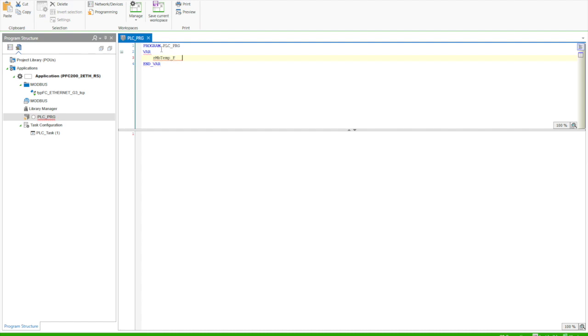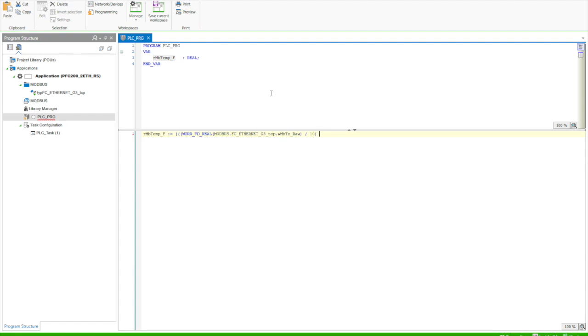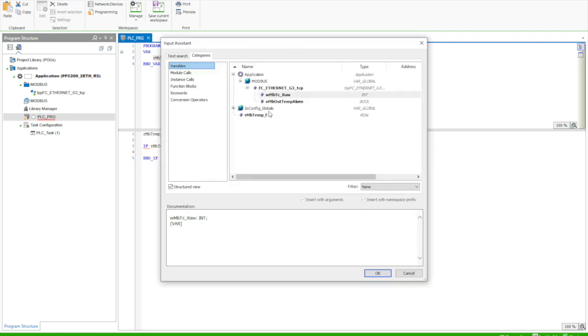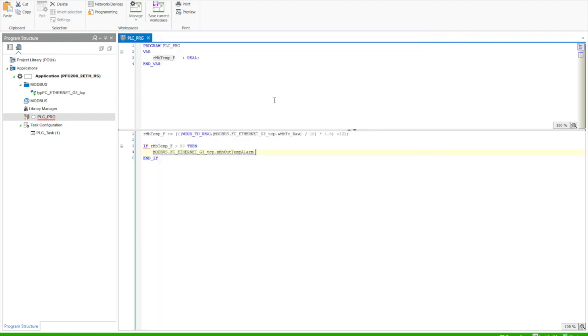All we're going to do is convert the input from the thermocouple, which is degrees Celsius times 10, as it's a whole number value. So we just need to convert that to Fahrenheit. So I'm going to divide it by 10, multiply it by 1.8 and add 32, which is the conversion to Fahrenheit. Then we're just going to set a condition that if the temperature is over 80 degrees, then our output alarm will be true. Otherwise, our output alarm will be false.